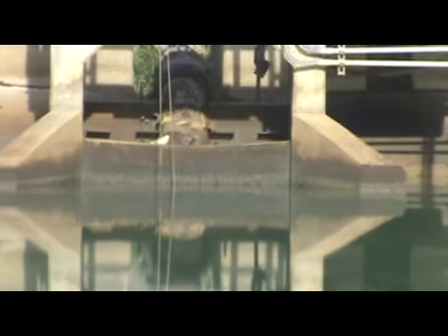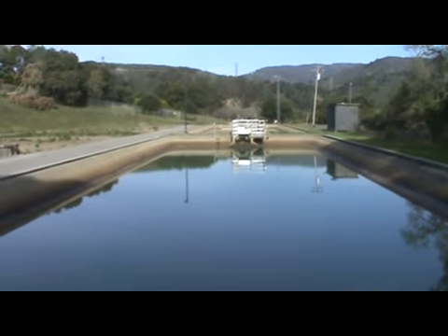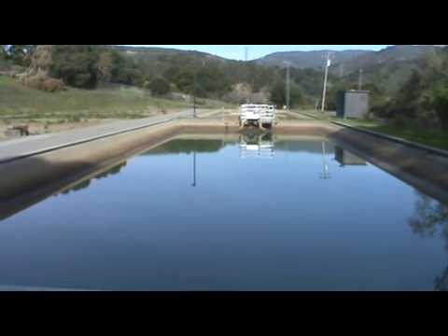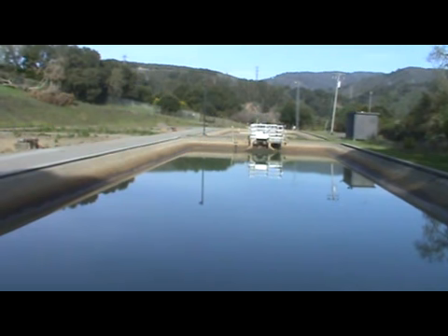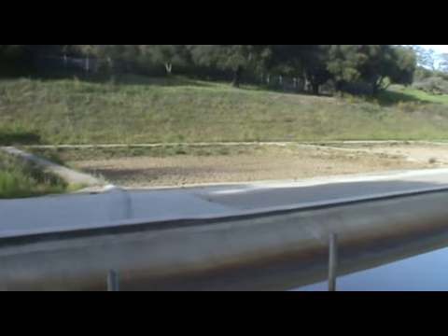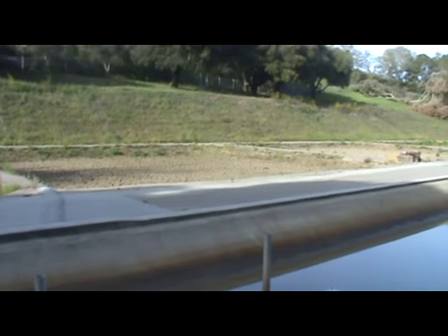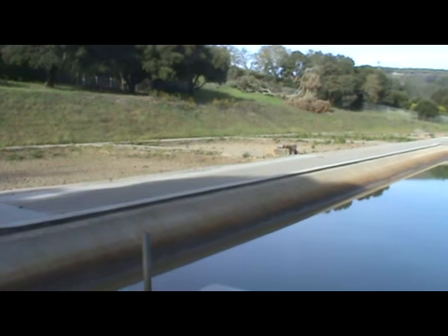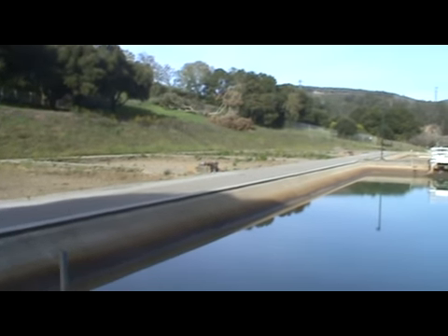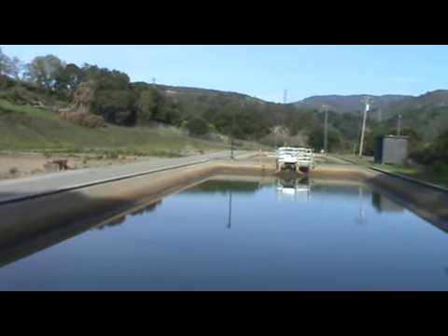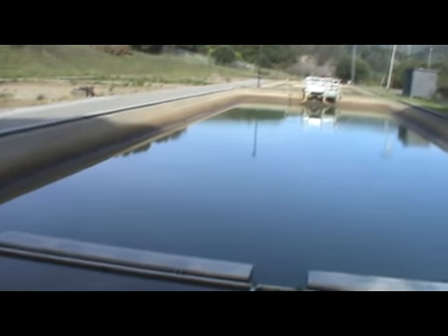Through some influent piping right there, it enters these lagoons. It has a little bit of time to settle in these lagoons, and then on timer, there's an arm that scrapes the bottom of this, and sludge pumps underneath pump to these drying beds over here, which allow the water to settle down and the dirt and everything to dry in. Now once these get filled up, they just get cleaned out and the dirt gets hauled away. So that's what happens once that water leaves the backwash process.